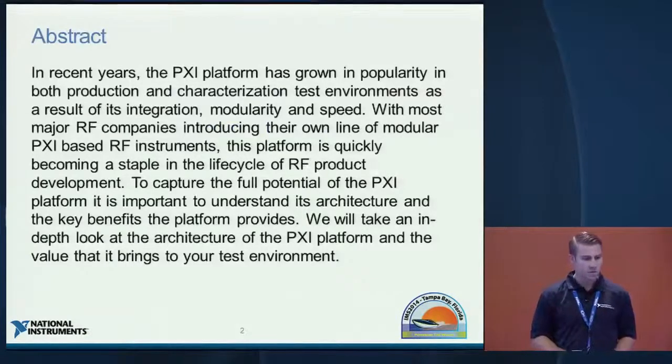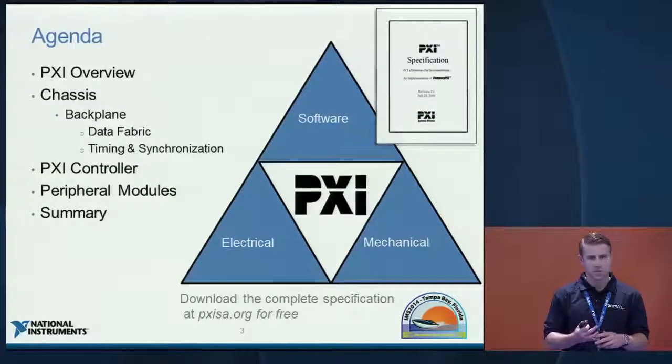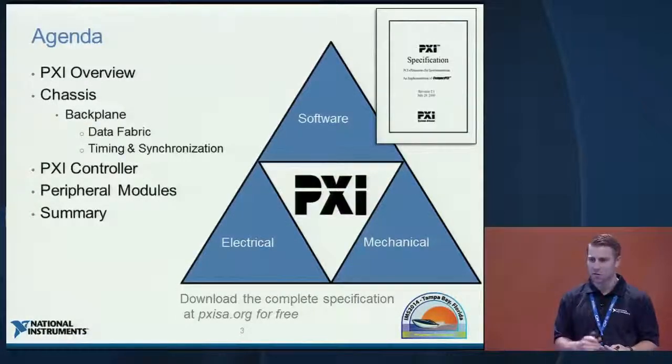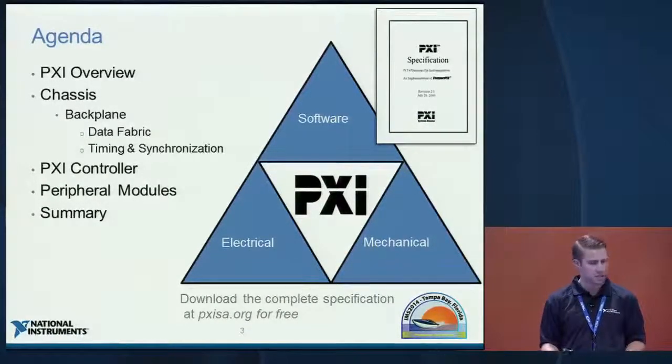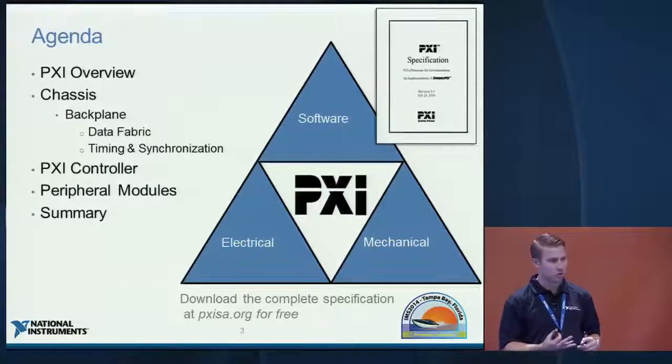At a high level, I'm going to walk through what I call the anatomy of a PXI system — there's a loose association with the human body. We'll walk through the three main components: the chassis with backplane data fabric, timing and synchronization, PXI controllers, and peripheral modules. The PXI specification is managed by the PXI System Alliance, a group of about 70 different instrumentation companies. You can get the spec for free at pxisa.org, which defines the software, mechanical, and electrical specifications for the PXI standard.